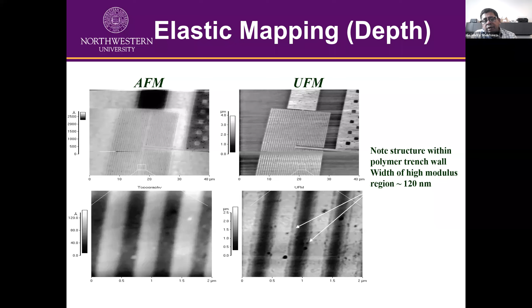Rather than oscillating the sample, we are also oscillating the probe simultaneously at two different frequencies. We use piezo crystals to excite those out of plane vibrations. The cantilever is basically a reference cantilever because it's made of the same material, so the frequency will not shift. So when these two oscillating objects interact with each other, they create a difference frequency. And that frequency is low enough that the cantilever can easily pick up those modulating waves, and we can extract the subsurface information, because when you excite the sample, if it has any defects underneath, it can delay the phase. It can change the phase of that wave that's reaching the surface. So basically we are measuring the change in the phase. So it's non-destructive, it's depth sensitive, it has pretty good lateral resolution, and it's very sensitive to phase perturbations.